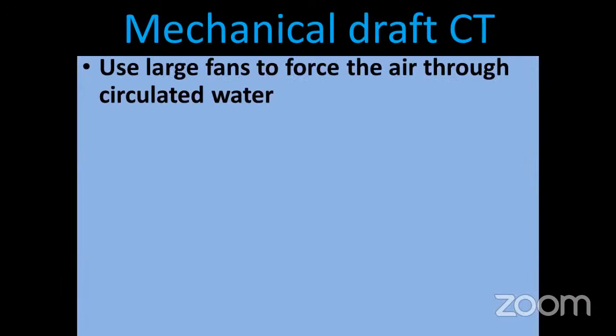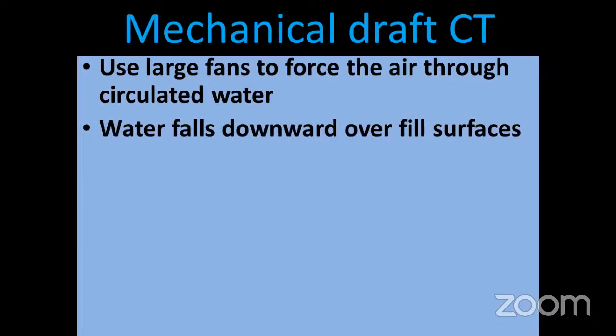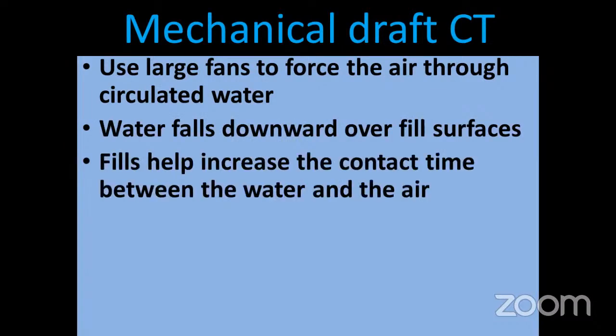We use large fans to force air through cooling water, circulated water. Water falls downward over fill surfaces. Fills actually separate the water. In the huge cooling tower, sir, actually the water is made to fall from around 20 meters or less, I think. Actually, the vast height of that cooling tower is empty. The water is falling from the lowest point up to around a height equivalent to a 5-story building, that's all. From that level, water is made to fall.